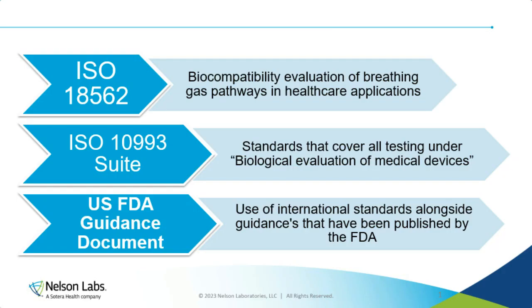Over the previous decades, the ISO 10993 International Standard Series has been the overarching set of standards that helps provide guidance on how to evaluate medical devices for biocompatibility. Many documents have evolved, and they continue to evolve. As such, the new ISO 10993-17 release is very anticipated. However, there has been a split in these overarching documents because of special cases of externally communicating devices, such as those that carry air or gas to the lungs. When a gas is the carrier of an externally communicating device, the risk profile is a bit different than if the carrier was a liquid, which is the suggested matrix of the ISO 10993 series.